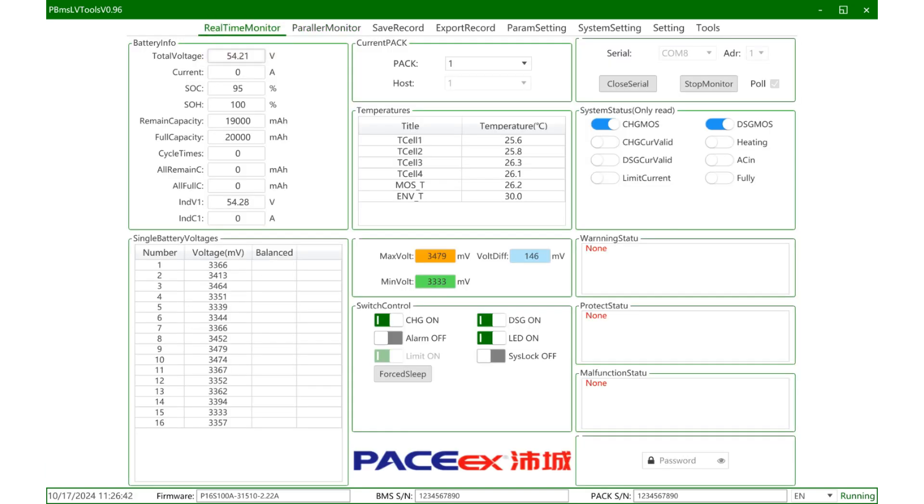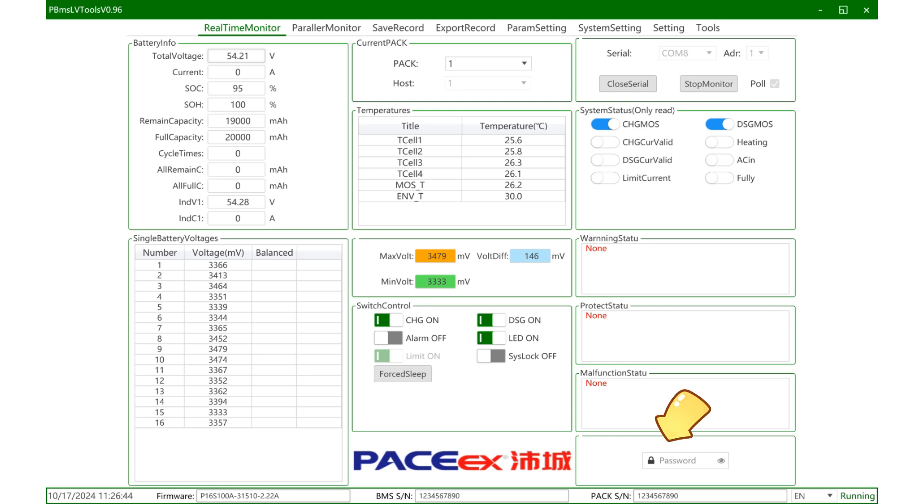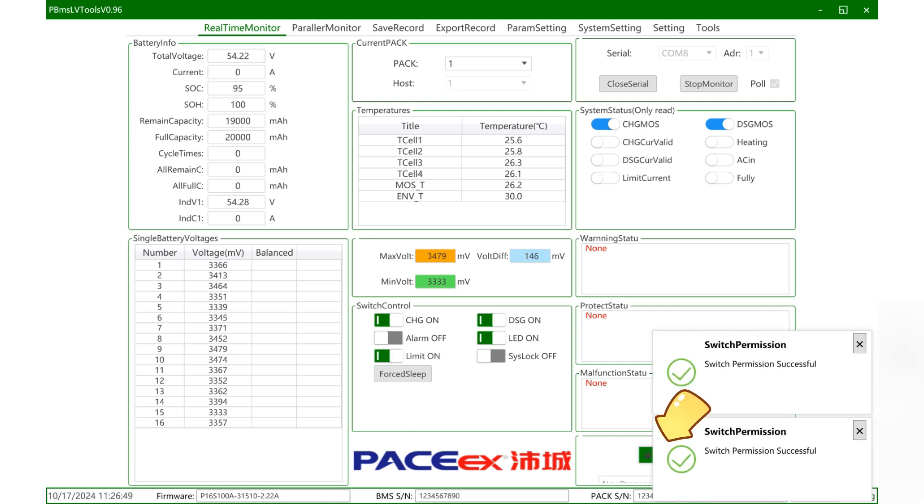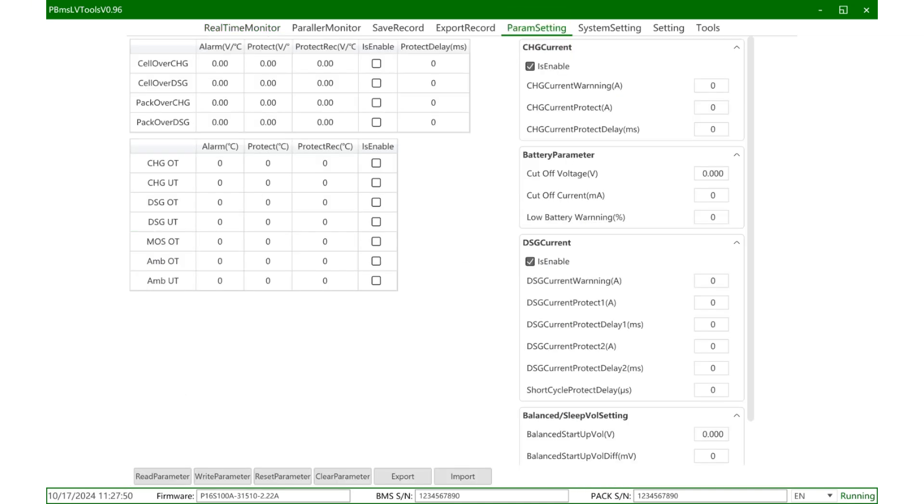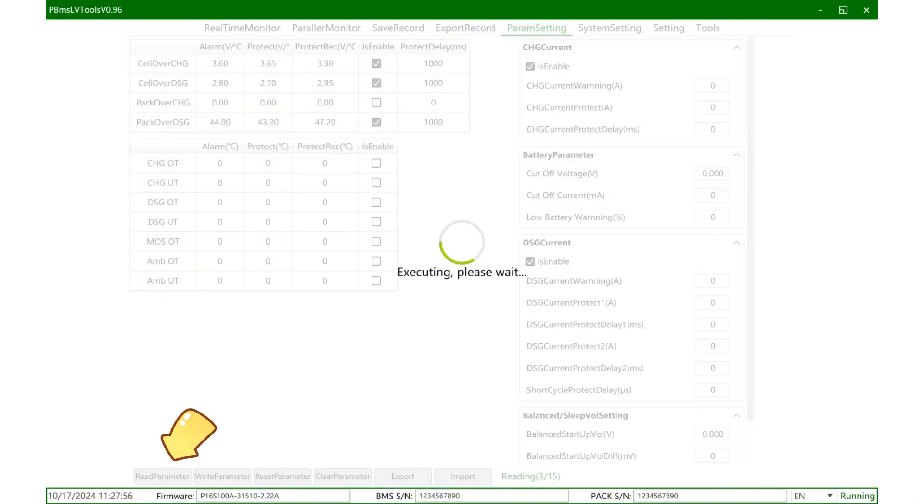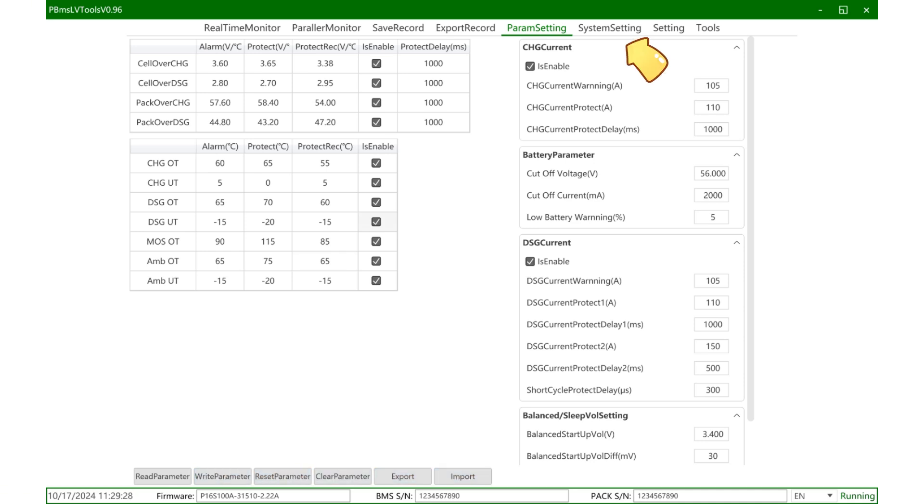If you need to read or set the parameters, you need to switch back to the real-time monitoring page and enter the host computer password. The host computer password is generally defaulted to one, two, three, four, five, six. Then click the parameter settings page, read or set the parameters of all options on this page. When you have set a certain parameter, you can click to read it again to ensure that the modified parameter has been set successfully. The setting and reading and writing of basic parameters can be operated here.